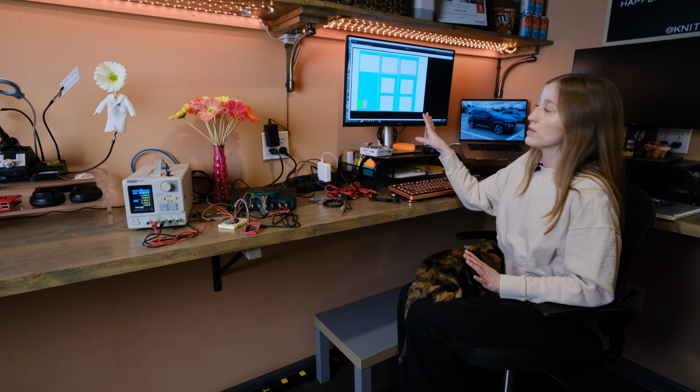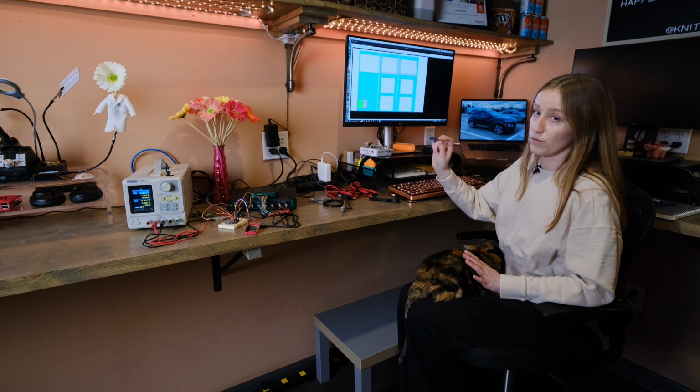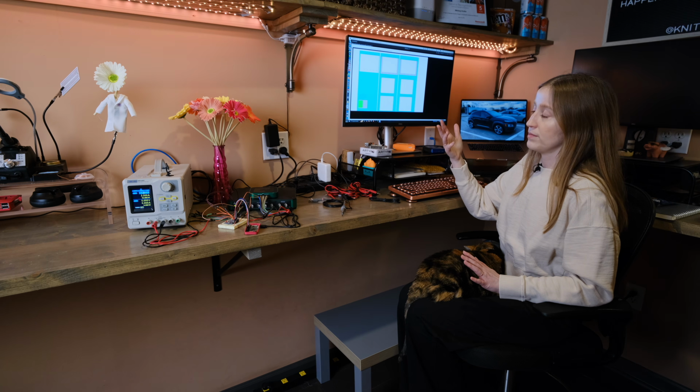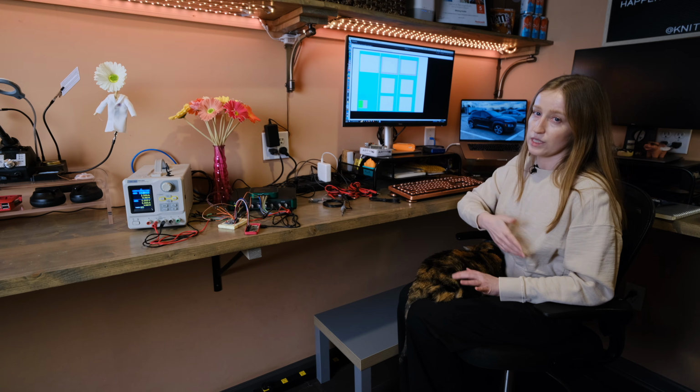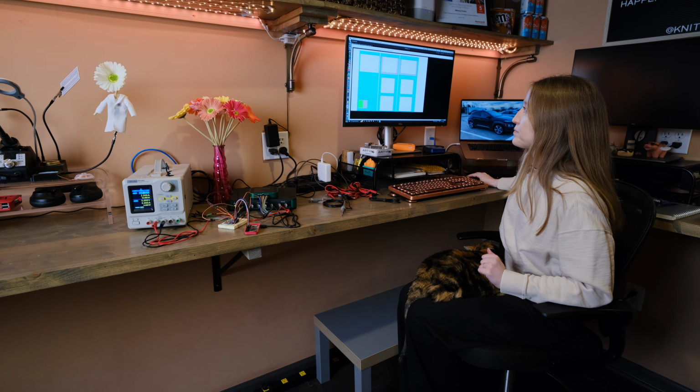And then I made my nice pretty button nice and big down here. Because of the way this runs in the sequence, I have the on-off button default to being on. When I turn it off, which I'll show in the sequence later, that's what triggers the sequence to move on. But it will stay running until I hit the off button.